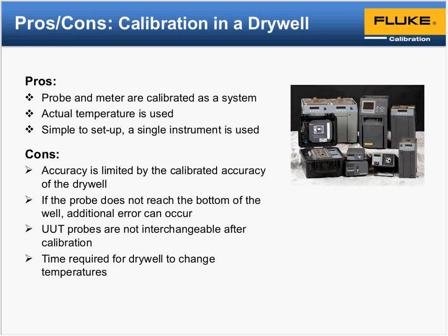All right. Component calibration, I'm an advocate of them based on the product side, because of the versatility in having each piece have its own characteristics. You can use that piece with different readouts, and so that's why I'm an advocate of that. And then you're looking at each piece, versus a system where you don't know where the error was contributed by the probe, or who knows, we've just held it in with the error.